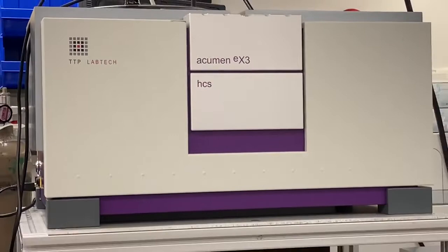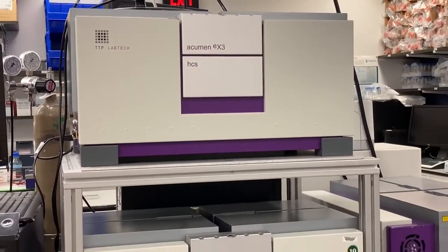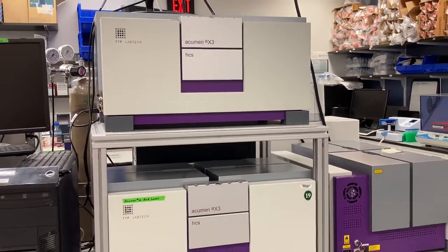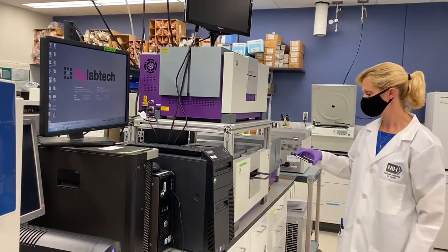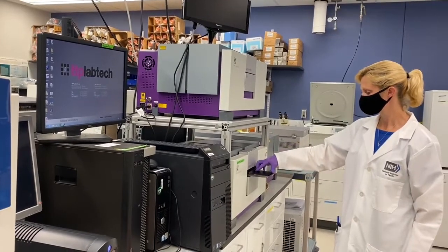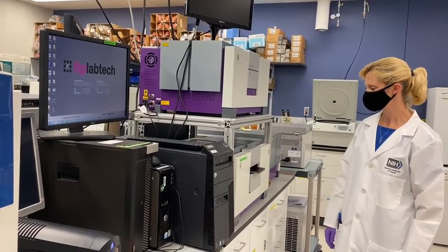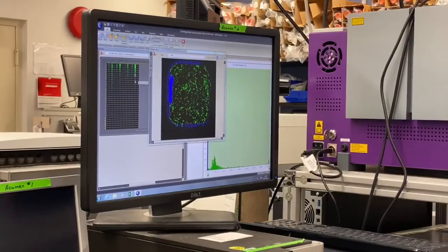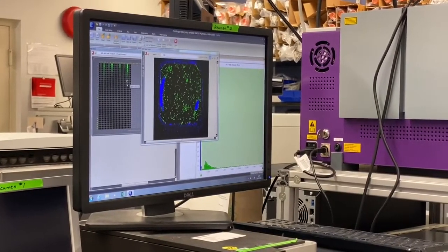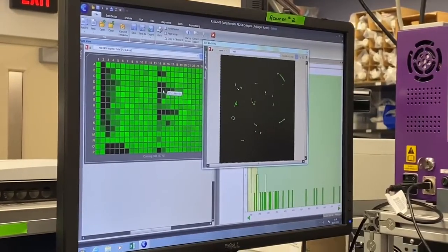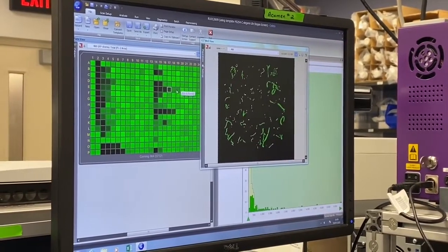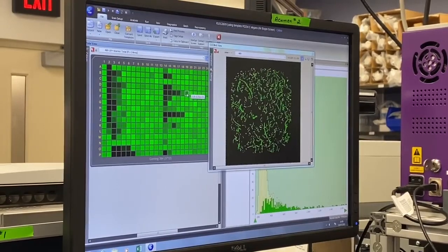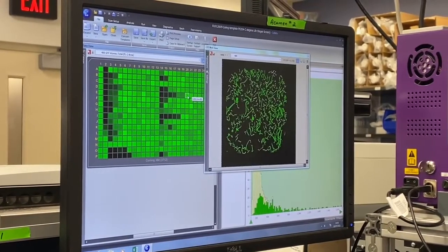The Acumen laser cytometer offers greater resolution than the previous whole well readers. Similar to flow cytometry, laser cytometry allows for the detection and gating of respective populations of adherent cells, beads, or model organisms including yeast and C. elegans, based on fluorescent intensity and size, and can offer enough resolution to assess protein translocation and distribution of the respective fluor. Distinct parameters can be selected and subpopulations identified and quantified concurrently during the read.